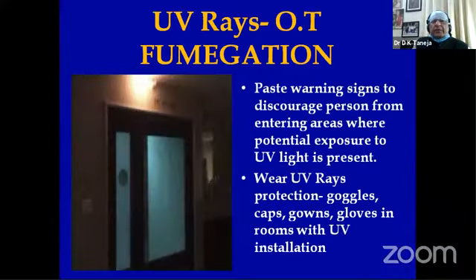Now, the most important, this is what we have been telling about the ultraviolet rays: the switch should be outside, there should be a warning there, that don't go and expose yourself to ultraviolet light. You have to put it on at night and switch it off in the morning. You must put on UV ray protection like goggles, caps, gowns and gloves, and then you go to the operation theater. That's very important.